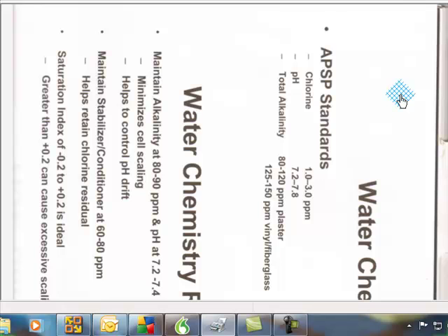It's your pool pump, your pool filter. All that sees water is seeing bad chemistry. And that's why your seals go in 6 months. It starts leaking, and if you don't see the leak because it's outside, and your motor bearing starts going because the leak got so bad it got into your bearing, pumps will burn up in 8 months. All right, I've seen it happen. I've seen pumps fail in 90 days because of bad water chemistry.